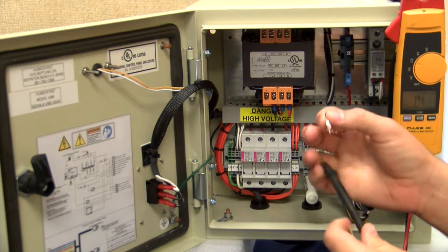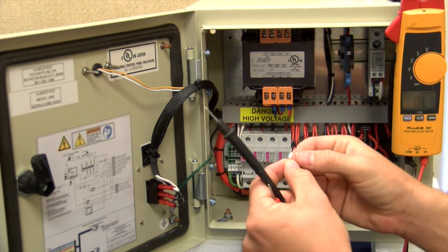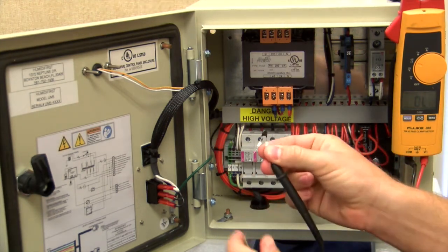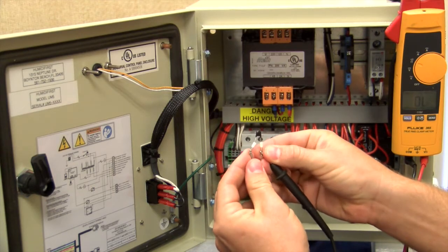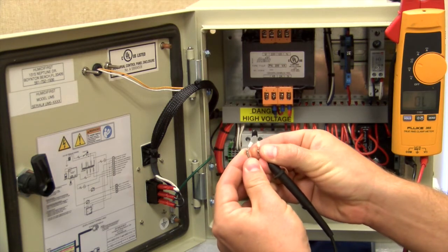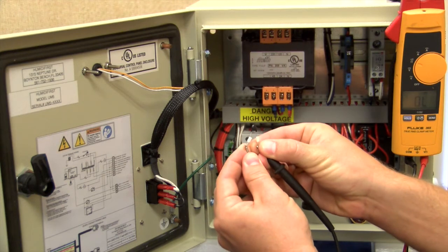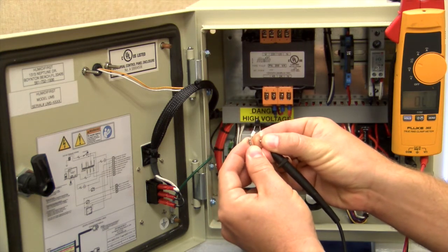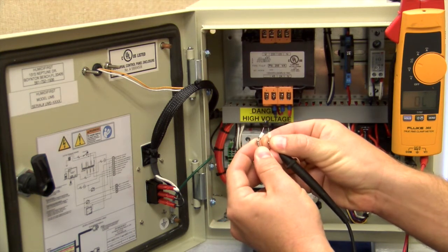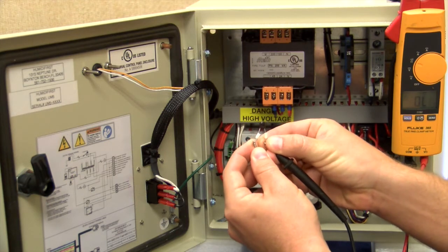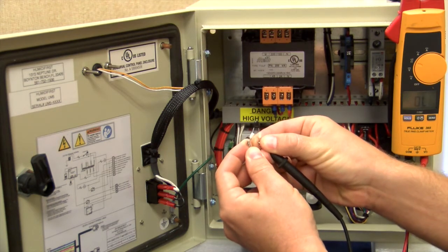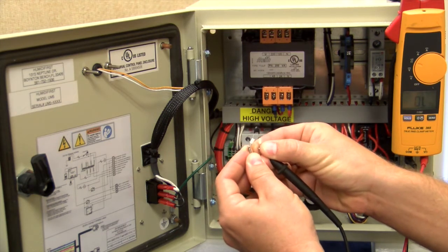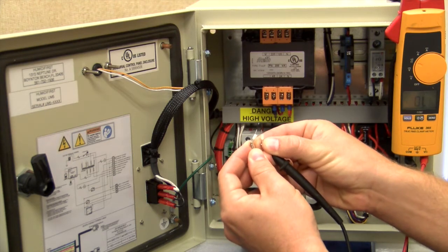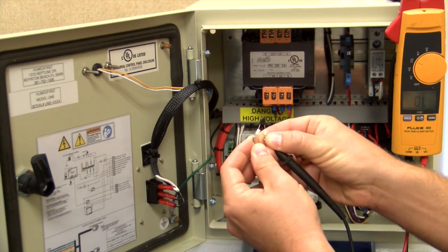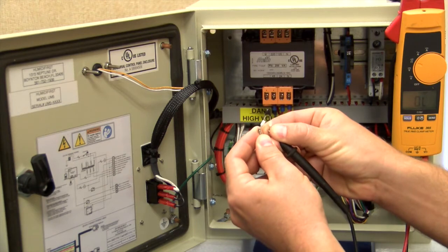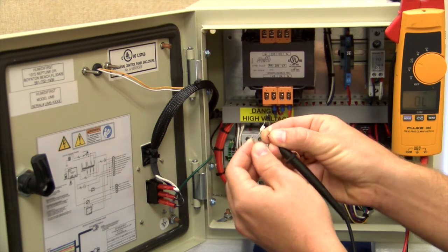To check for the continuity of this surge arrestor, simply take one prong on each one to make sure you don't get continuity across it. If you are getting continuity across it, you have a bad surge arrestor, and you're going to want to make sure to check your fuse. If you keep replacing a fuse with a bad surge arrestor, the fuse will keep blowing.